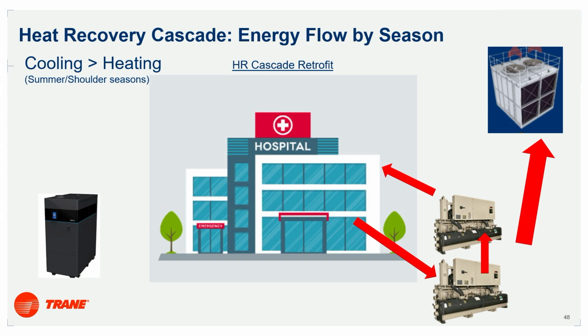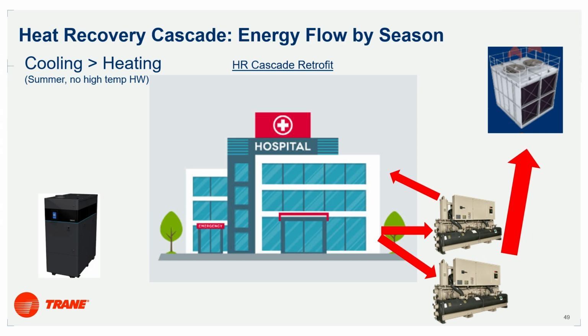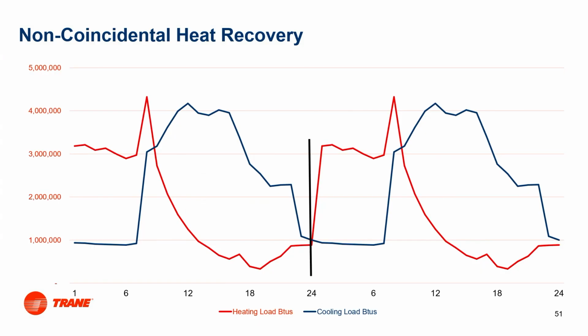So how would that work when the cooling load is greater than the heating load? Well, our boiler is going to be off. We're going to reject as much heat as needed for the heating load to that booster, and any remaining heat is going to go out through the tower. One thing that facilities are really liking the prospects of is that in the summer, if we don't need a heating load, that booster is just a chiller. So we're adding redundancy and resiliency to their cooling plant when they don't need hot water, because we can run that in a standard cooling configuration. And maybe they have a low temp load. Hey, let's get 120 out of that, deliver that to handle all the reheats, and then reject the rest of that heat out to the ambient air.